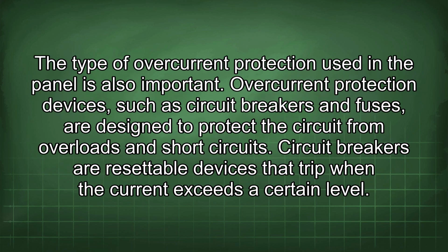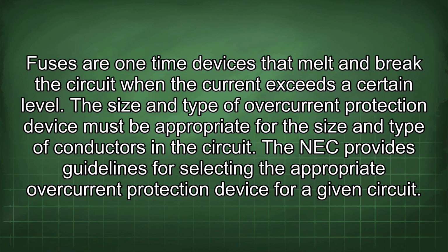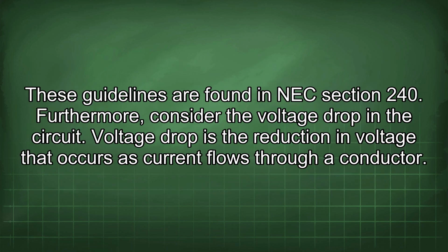The type of overcurrent protection used in the panel is also important. Overcurrent protection devices, such as circuit breakers and fuses, are designed to protect the circuit from overloads and short circuits. Circuit breakers are resettable devices that trip when the current exceeds a certain level. Fuses are one-time devices that melt and break the circuit when the current exceeds a certain level. The size and type of overcurrent protection device must be appropriate for the size and type of conductors in the circuit. The NEC provides guidelines for selecting the appropriate overcurrent protection device for a given circuit. These guidelines are found in NEC section 240.